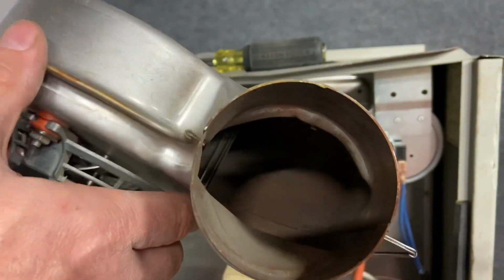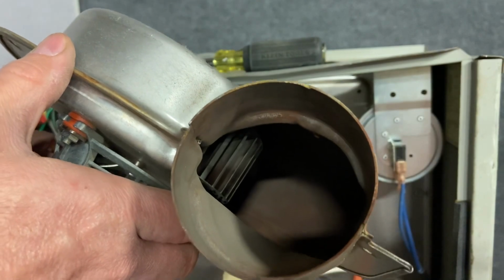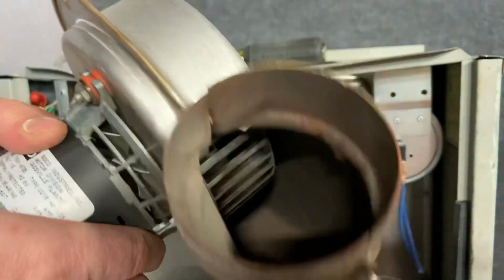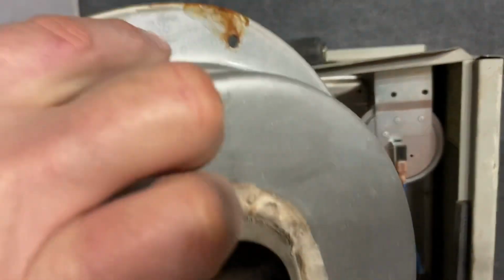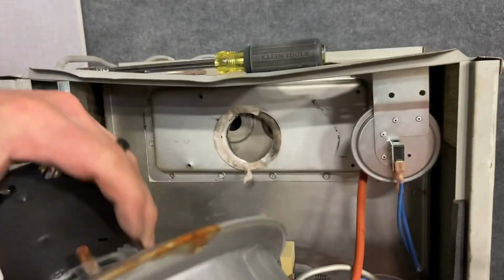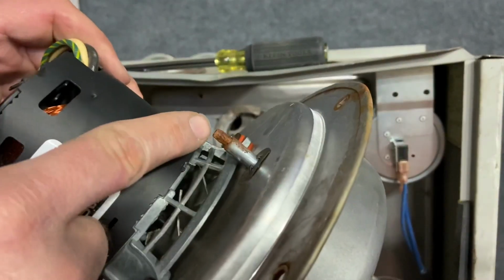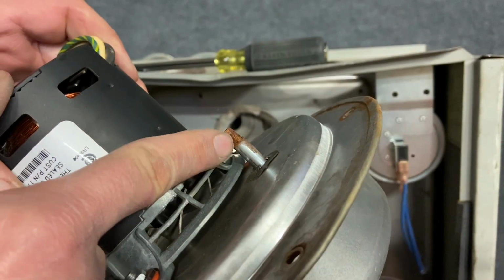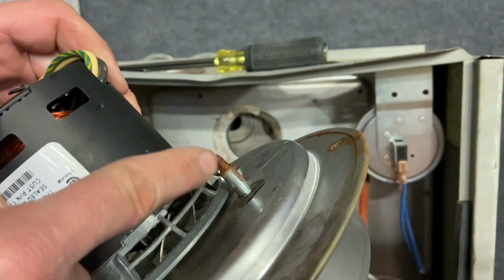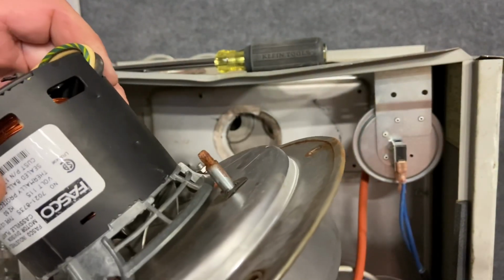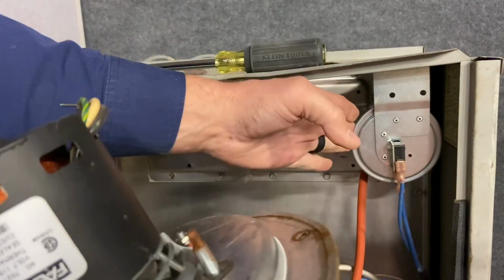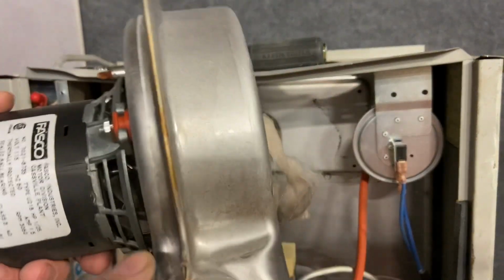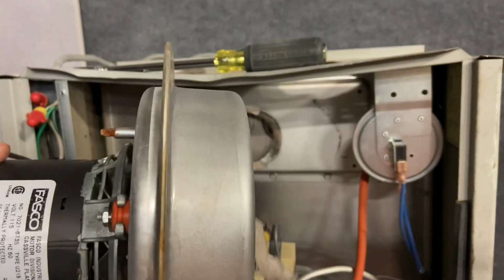Here, if we look into the very end of this, you can see also a significant amount of that rust that's in there, as well as rust here building up on the side. And this is where the vacuum port hooked up. And you notice there's a lot of rust there as well. Sometimes these will rust up and they will actually stop up the hose, so the pressure switch never even senses the vacuum. But this is our inducer fan assembly.